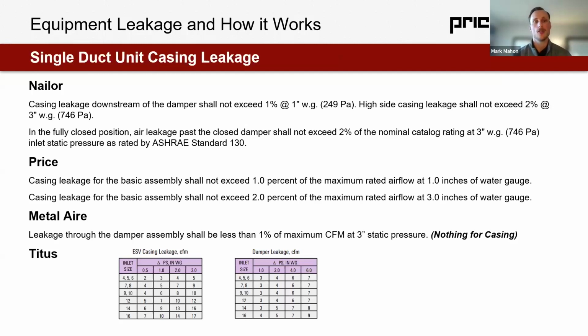Interestingly, Metal Aire only specifies damper leakage based off of seeing and reviewing their construction. I think they actually do it very similarly to us, but interestingly in their spec, there's nothing for the casing, which is maybe an oversight, I'm not sure, but is interesting, and I thought I'd point that out. Then we look towards Titus, and Titus manages it very differently. They manage it with a table of leakage values per inlet size. I will say, looking at Titus actual performance, or looking at the percentage and kind of doing some math to look at the table and compare it back to percentages, pretty much the same thing from Nailor and Price as well. Really no difference in construction or specification, just a different method of showing it.